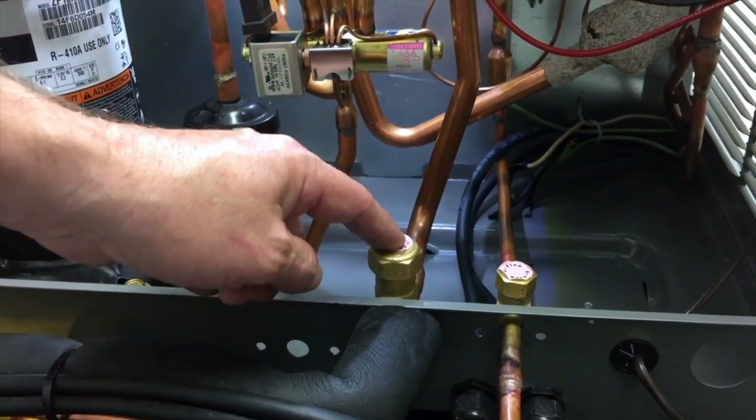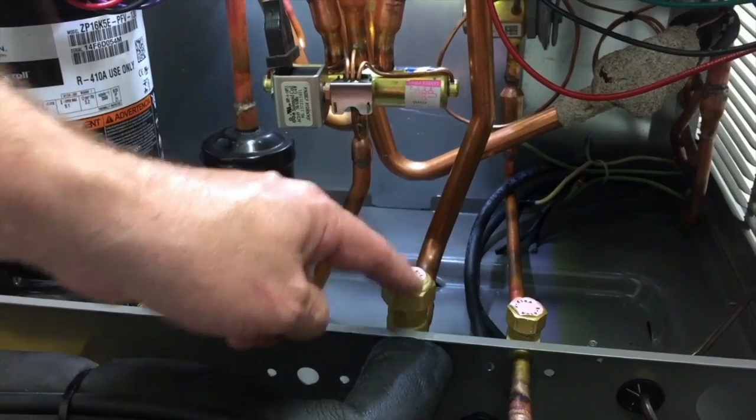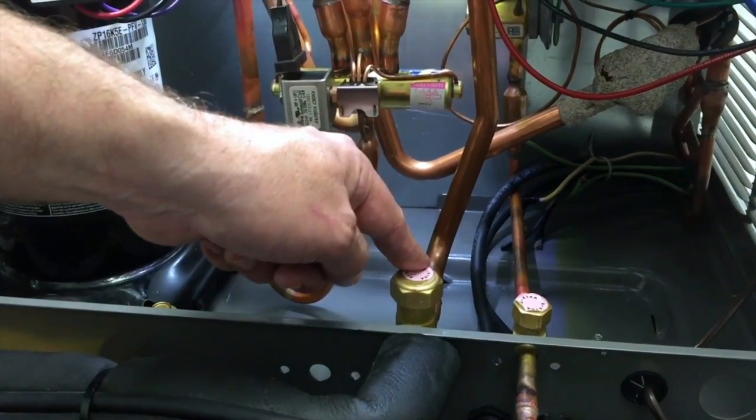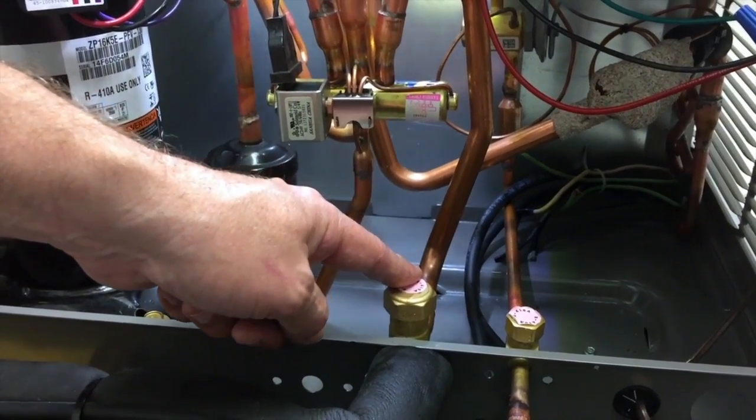We don't want to hook up to this line, which is called the vapor line on a heat pump system. The reason this is the vapor line is because in the reverse cycle, in the heating cycle, the hot gas can flow out this way. In the cooling cycle, the cool suction gas flows back this way, so this line can be either high pressure or low pressure.